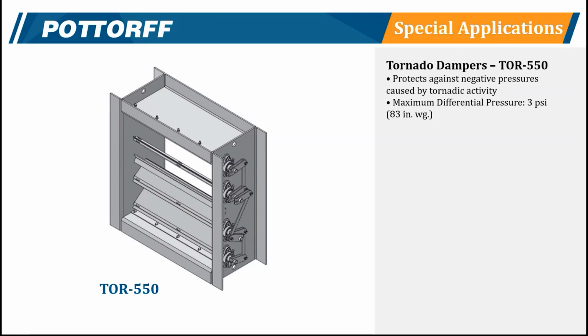One other special application damper that we offered last year was a tornado damper. Now, this is in theory a lot similar to our blast damper, but it is configured a bit differently. It actually protects against negative pressures caused by tornadic activity to protect the ductwork. So it's actually a force that's pulling against the ductwork rather than an explosion or some type of blast that's hitting the outside of the ductwork.